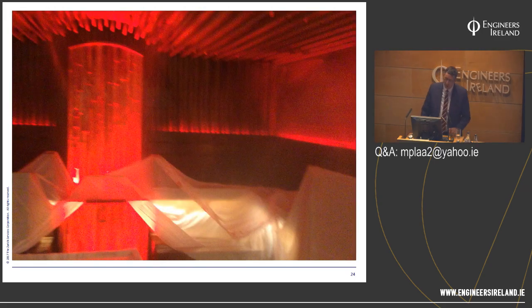And another example is a sauna. It's a very expensive sauna in someone's house as well, where they've got water mist within that environment. Again, we test every single sauna system we come across. And again, we've had multiple failures in this environment. Quite a simple water mist system off the town's mains, where we've got insufficient pressures and flows and blocked nozzles as well.